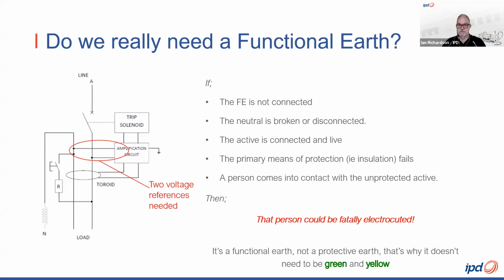That's very true, Fred. But remember, this is a functional earth. It's not a protective earth. And that's why it doesn't need to be green and yellow. The standards are clear. A protective earth must be green-yellow conductors, and we're all very familiar with that. It's spelled out very clearly in AS3000. However, the standard's also clear that a functional earth that is provided to ensure the correct operation of electrical equipment does not need to comply with the requirements of the main and protective earthing conductors.